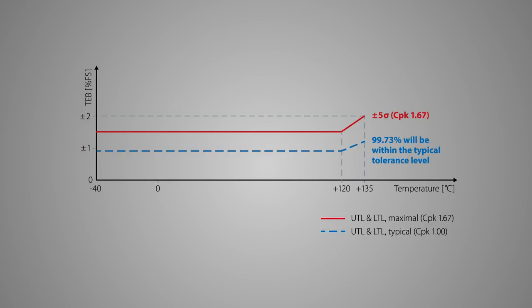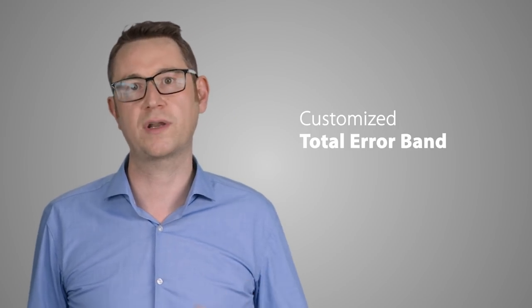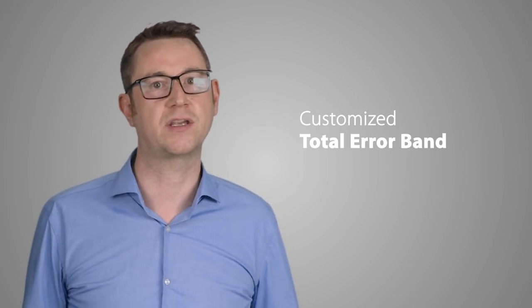The blue line shows the typical value that corresponds to 3 sigma limits and CPK of 1. A measurement of the exhaust back pressure of a running engine needs to be more accurate at high temperatures, where the measurement in a cooling application requires an accurate measurement at lower temperatures. Therefore, Danfoss can provide customized total error bands according to the requirements in the application.